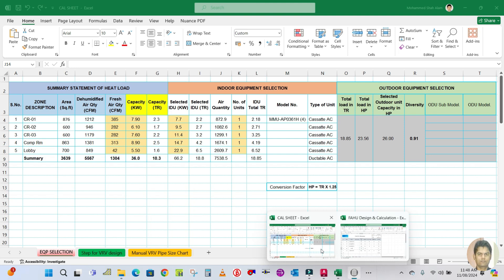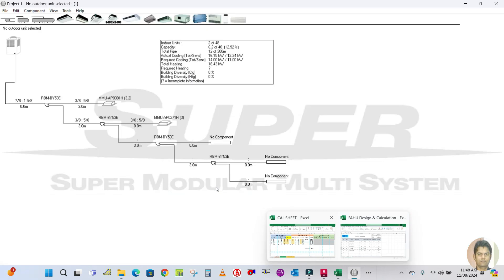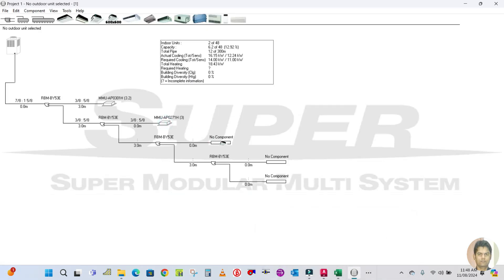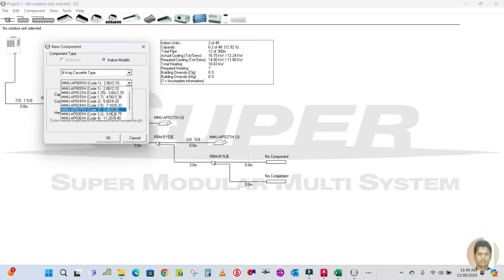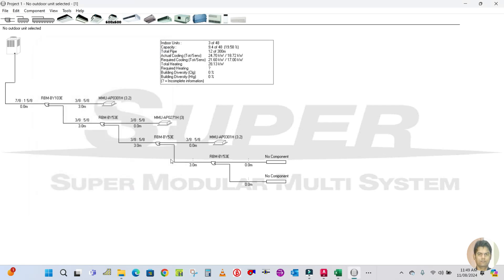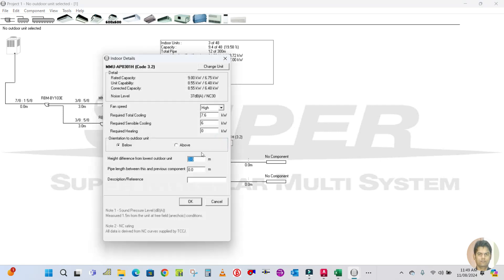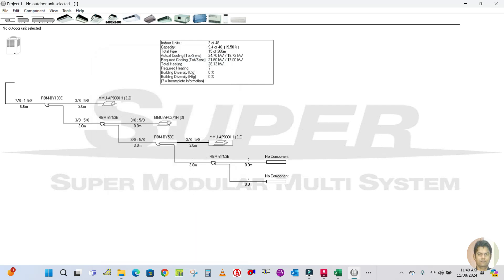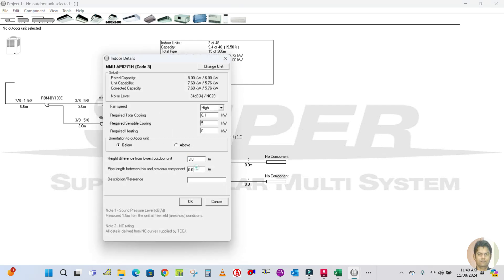Classroom 3 requires 7.6 kilowatts, so you have to change the unit to 9 kilowatts. Update the required cooling to 7.6, sensible to 6, click OK. Pipe length is 3 meters — click OK and update to 3.